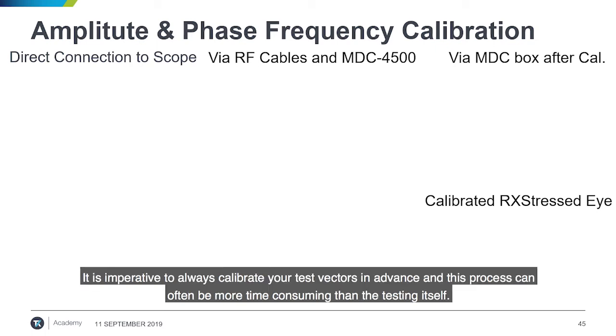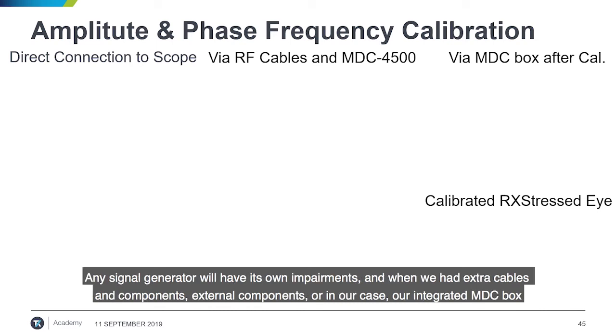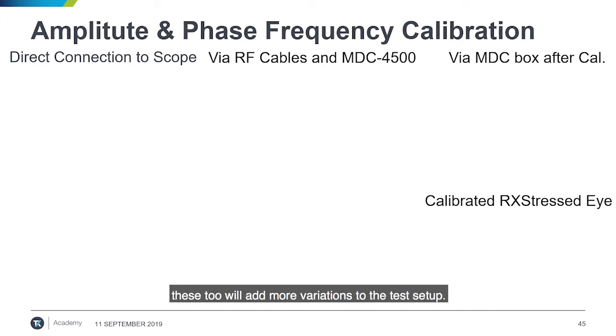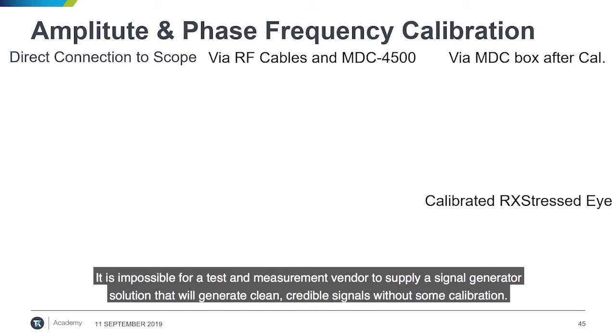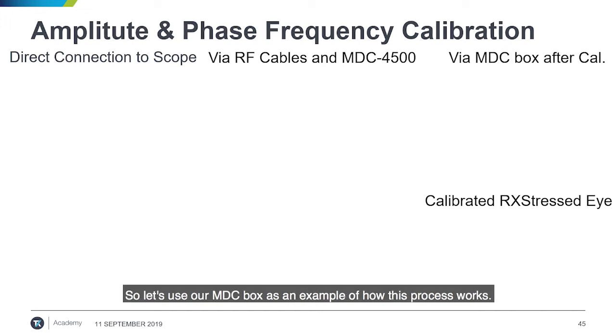It is imperative to always calibrate your test vectors in advance, and this process can often be more time-consuming than the testing itself. Any signal generator will have its own impairments, and when we add extra cables and components, be it our external components or in our case, our integrated MDC box, these too will add more variations to the test setup. It is impossible for a test and measurement vendor to supply a signal generator solution that will generate clean, controllable signals without some level of calibration. So let's use our MDC box as an example of how this process works.